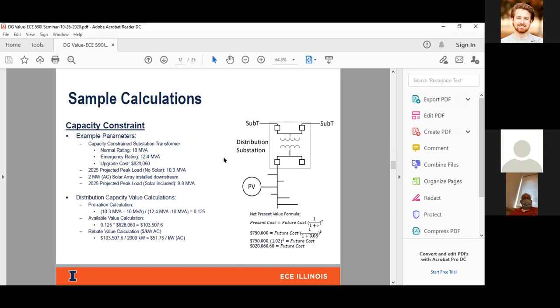So for an example, if we take this scenario where we had a constraint at the substation transformer, and we have a DG installed downstream of that transformer, the substation transformer has a normal rating of 10 MVA and an emergency rating of 12.4 MVA. If I wanted to upgrade this specific transformer, based on what Ameren has paid in the past, the upgrade cost would have been around $800,000. We look at a 5-year horizon for the load forecast. That's our planning criteria established here, and a lot of utilities use the same methodology. This is consistent across utilities in the United States.